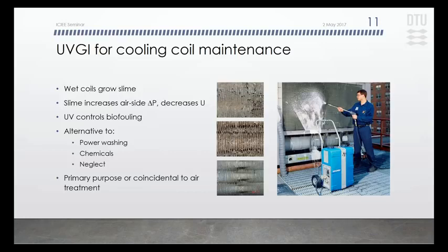When you have a coil that's doing dehumidification, that's wet much of the time, it will collect microorganisms, and slime will grow on it, bacteria, fungi. That will reduce the space between fins, increase pressure drop, and it also acts as thermal insulation and will decrease the heat transfer coefficient. So if we can control that, we should be able to get some improvement in energy performance, maintain intended airflows, and perhaps also prolong the life cycle of the coil.